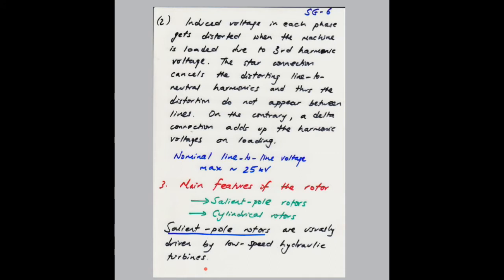And the second reason why we connect it in star is that the induced voltage in each phase normally gets distorted when the machine is loaded, due to third harmonic voltage. So what happens when you have a star connection is this type of connection cancels the distorting line-to-neutral harmonics, and thus the distortion does not appear between the lines, right? If you have a delta connection, the harmonic voltages will add up upon loading, and obviously then it will distort your output voltage. So that's the reason we use star connection for a generator on the stator side.